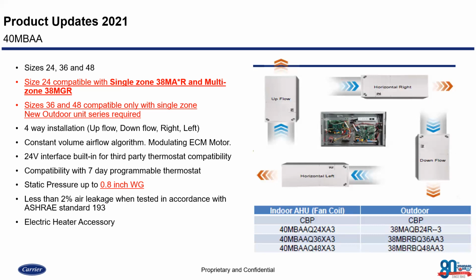Essentially, it was designed for a residential application where we're taking control of the space, obviously with ductless equipment, but we're still offering a thermostat that might be familiar to our customers, and we'll get into what thermostats we can use with that 24-volt interface. This offers static pressure up to 0.8 inches, but it's important to note that it does not come set up with this max static pressure from the factory. There are 2 ways of setting that, which we'll get into shortly in the next few slides. Testing showed less than 2% air leakage when tested in accordance with ASHRAE standard 193, and it comes with an optional electric heater accessory with its own dedicated part number specifically for these 40 MBAA vertical air handling units.